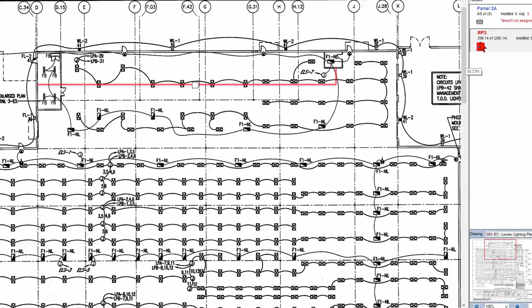I also have a linear measurement at 206 feet. I may want to drop, let's say the deck is up at maybe a 30-foot ceiling, or let's say it's even a 22-foot ceiling, and I want to drop down to the top of the panel board. That would leave 18 feet vertically. And before I finish the measurement, I can right click and add the constant of 18 feet at this end of the feeder, and right click and add 18 feet at that end, and have a more usable connector to connector measurement on the feeder.